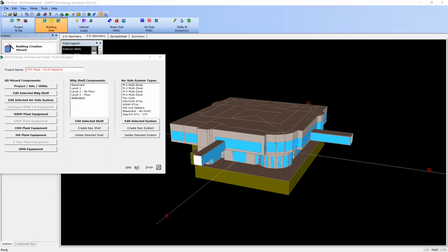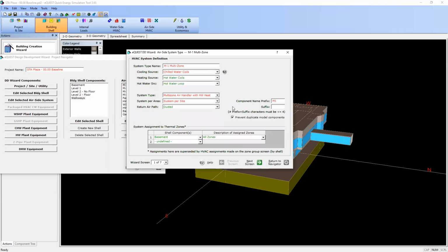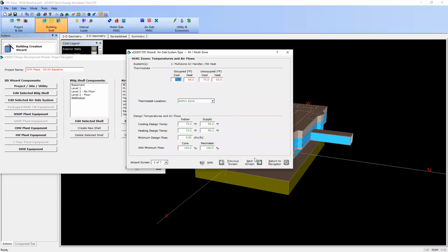If we go into the multi-zone, I can define things like what's my cooling source? Well, it's a chilled water coil. What's my heating source? It's a hot water coil. And then what type of system do I have? So we have all these different options. In this case, it's a multi-zone air handler. I can plug in my space temperature set points for occupied and unoccupied. And this program also has the ability to give different seasons. Like if I had a school, I could set up a summer schedule and a school in session schedule, which would give me 2 rows of set points that I could work with.